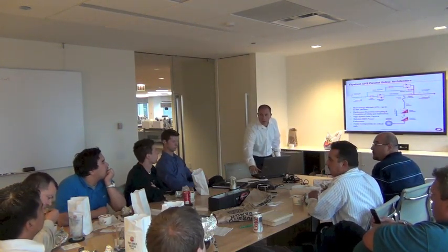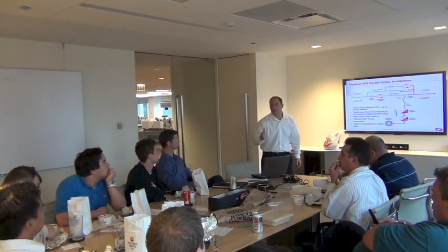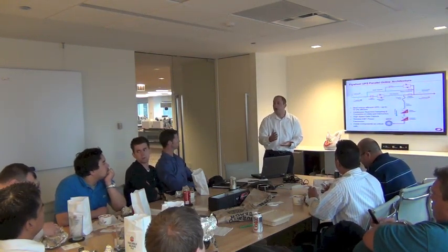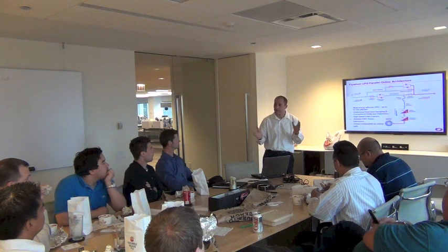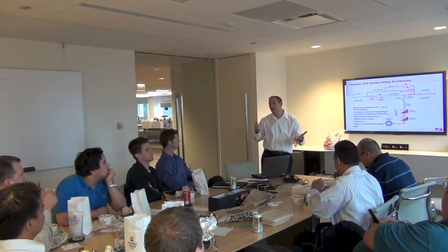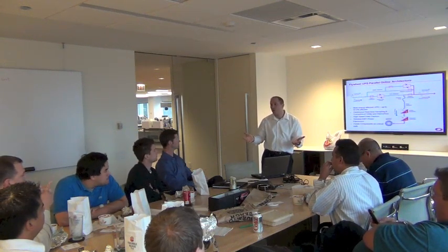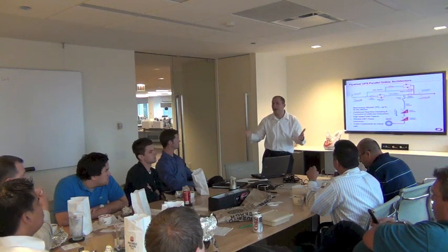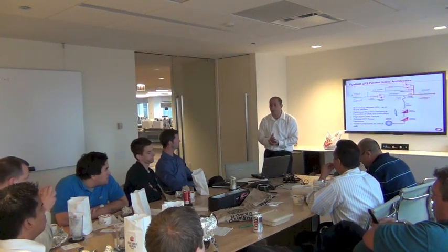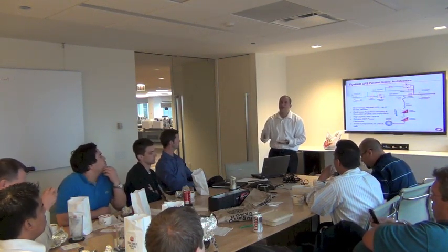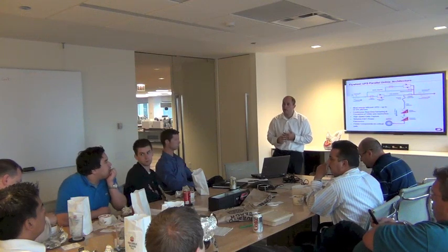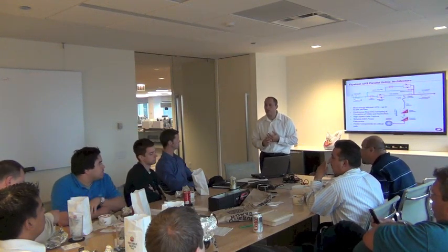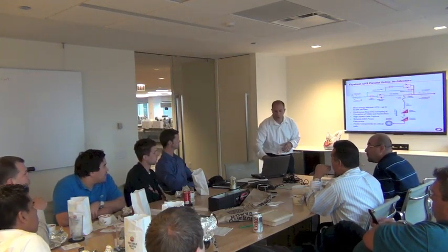What's the runtime on your UPS or on the flywheel? It's 14.5 seconds at 100% load. And obviously, if you have, let's say, a 600 kVA UPS, you can also add a redundant flywheel for redundancy or additional ride-through time. If you had a 600 N+1, for example, it would be 21 seconds at full load, and it's very linear. So when you say redundant, you mean you can connect 2 flywheels to 1 choke? What do you mean by redundant flywheels?